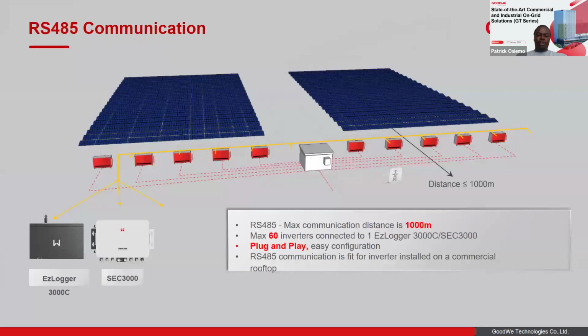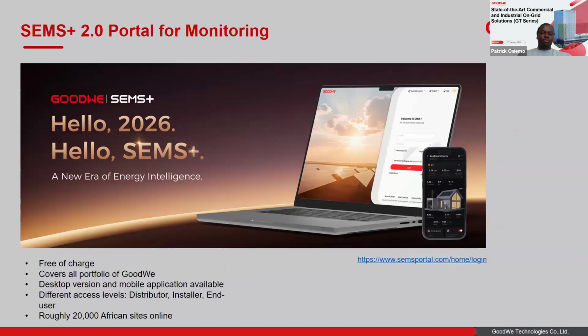If you're doing very large PV plants, you'll mostly focus on Modbus RTU or RS-485 communication. When you combine the GT series with the SEC3000 control box, you can connect up to 60 inverters. The distance between the control box, the SEC3000, and the EzLogger 3000, or between the SEC3000 and the GT series, can be up to 1,000 meters. This is a robust communication method for C&I applications, with up to 1,000 meters between the control box and the GT series, and all of this can be comfortably monitored using SEMS Plus version 2.